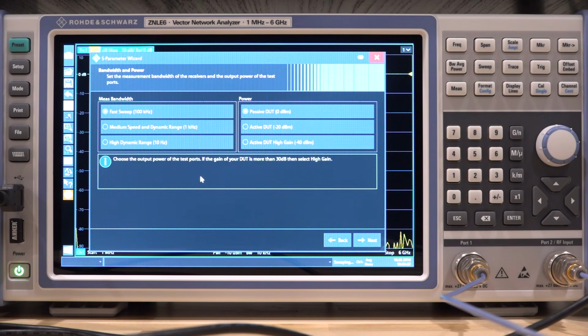And here we can set the IF bandwidth of the instrument. Now, if you set a very large IF bandwidth, the instrument will be very fast, but it will not have as much dynamic range. If you do a very fine IF bandwidth, the instrument will slow down significantly because it needs to gather more energy in order to compute the S parameters, but at the same time, it will have a much higher dynamic range because the IF bandwidth is so much smaller.